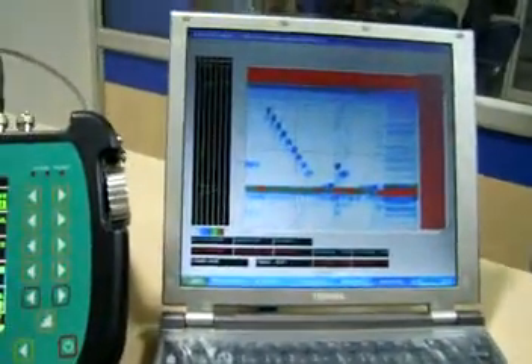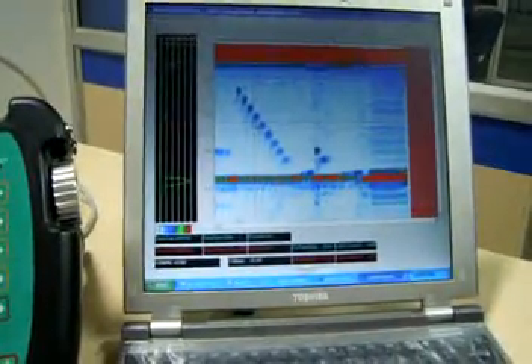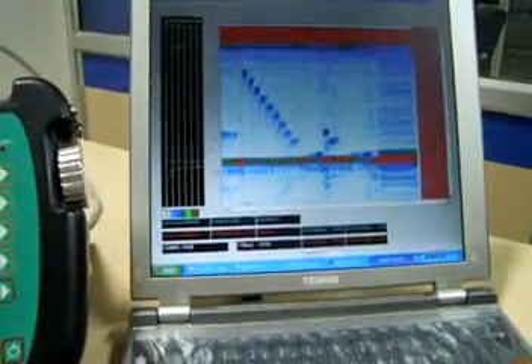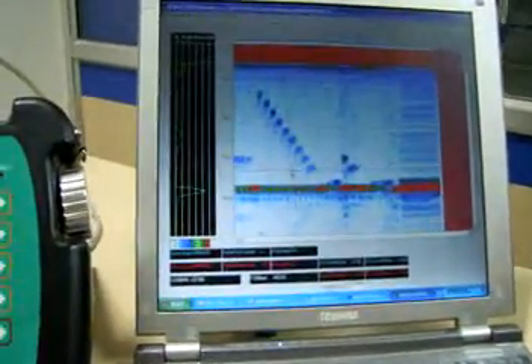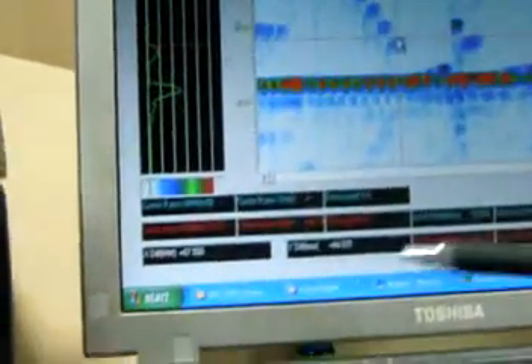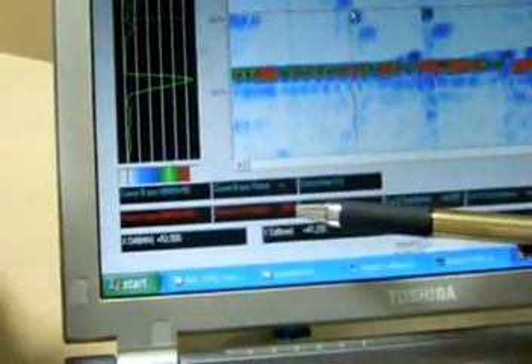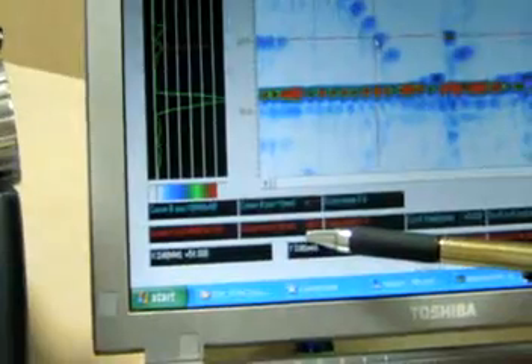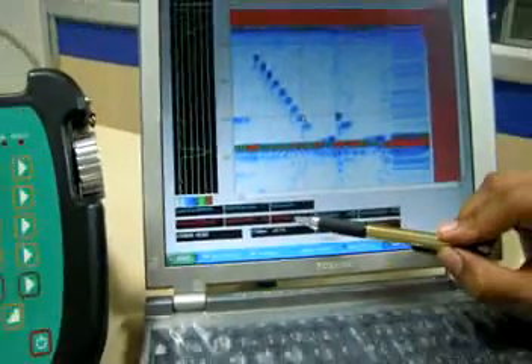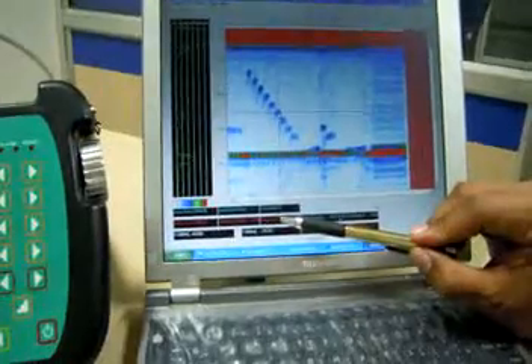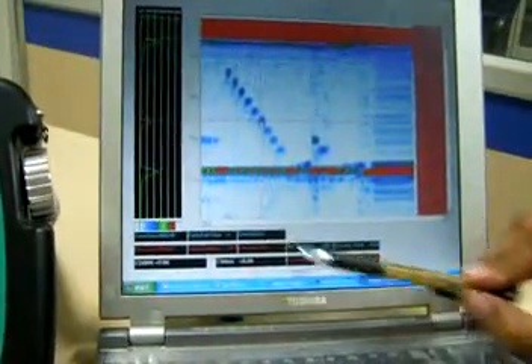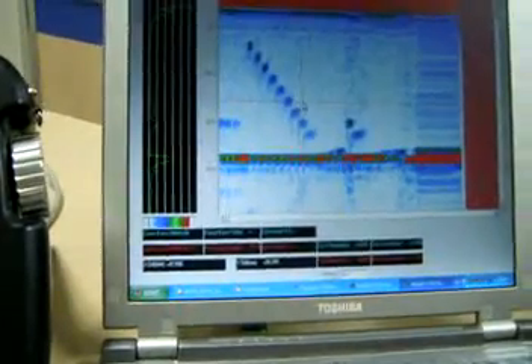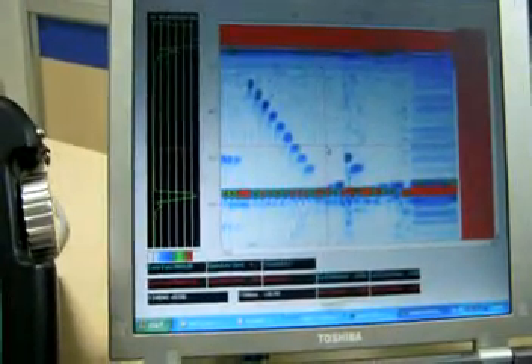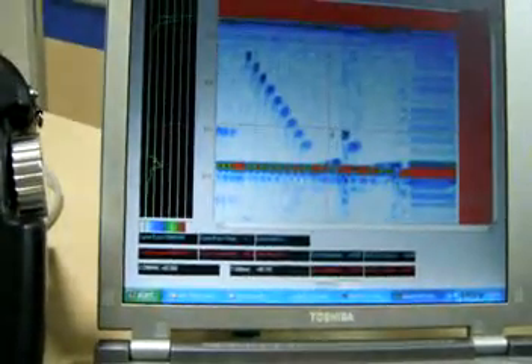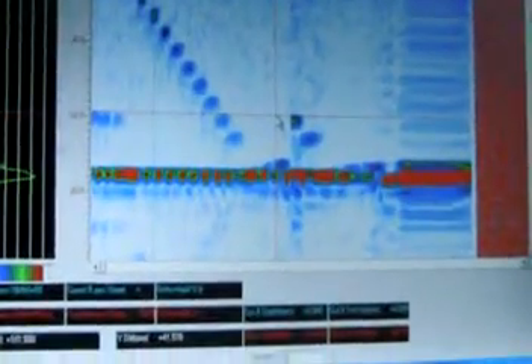You can see the B-scan view of all the holes and the back wall, and the cursor. Now when we move the cursor, the values of X and Y can be seen, so any distance. As the data was encoded, the probe position information is always available, and if the length of any defect is to be measured along the scanning direction, that is also possible.